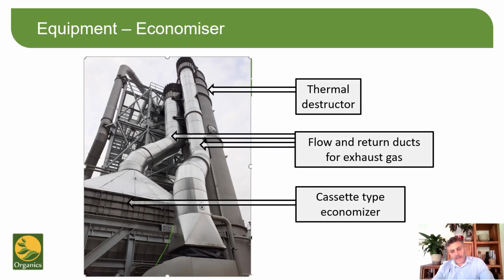A hot gas fan takes exhaust gas from the thermal oxidizer and moves it through the economiser. The temperatures are carefully controlled to ensure the economiser does not overheat, but works at an optimum temperature. The exhaust gases then leave the economiser and are returned to the top of the thermal oxidizer, which, as I mentioned before, provides a single discharge point for all products of combustion, making monitoring of these emissions much easier.